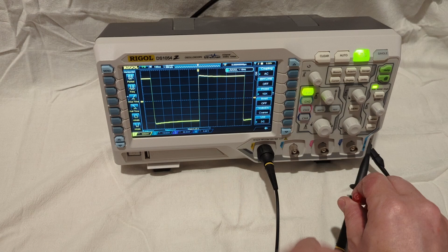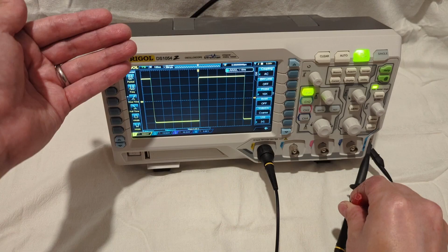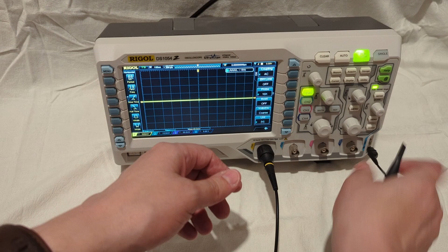But basically, you just need a small screwdriver, and you can start to adjust the compensation by just turning this screw. And you can see up here that the waveform shape is going to change as you turn that screw. So it'll either be too high or too low, depending on which way your compensation is off. And you just want to adjust that until you get about a square wave. You want to get it as nice looking as possible. The shape of the wave here is going to significantly impact your measurement capabilities and what exactly you're going to get out of your scope. So now that we've compensated our probe, we know that it is working the way we expect it to.